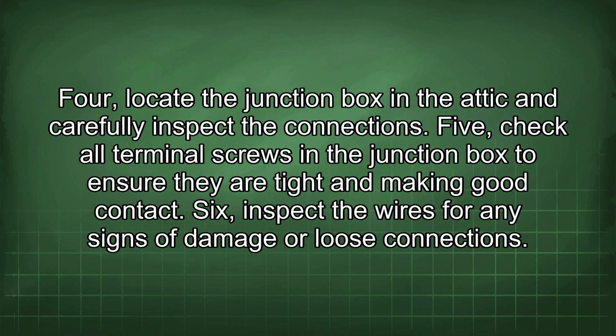4. Locate the junction box in the attic and carefully inspect the connections. 5. Check all terminal screws in the junction box to ensure they are tight and making good contact. 6. Inspect the wires for any signs of damage or loose connections.